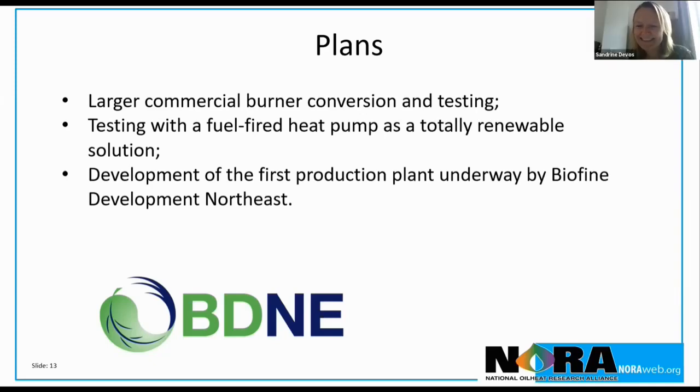Alexander, you want to jump in? Yeah, as I was referring to a bit in my presentation, I didn't go into the technical details. HVO, as with a synthetic fuel, you can actually set the cold flow properties more easily than with other fuels. It takes a little bit of effort and makes it more expensive, but I can't do the calculation off the top of my head. It's around below 0 degrees Fahrenheit. So we're around minus 27 centigrade up to minus 35 centigrade. That's the cold flow properties that you can get with HVO. But not every HVO can do that. That is clear. It needs a commitment from the producers. So these quantities will be limited around the globe, but there is a solution from the same feedstock and the same type.